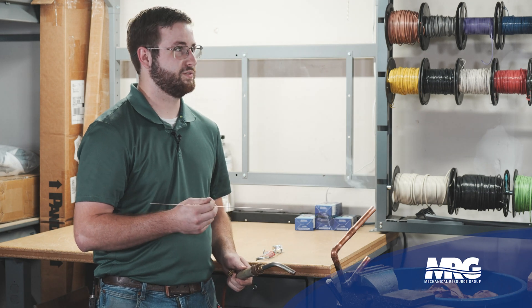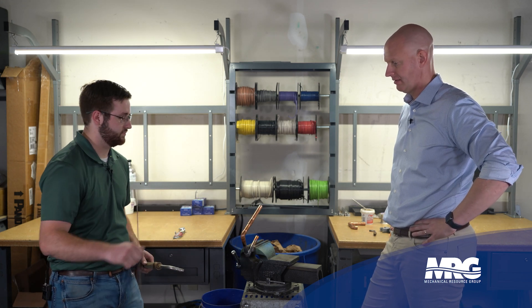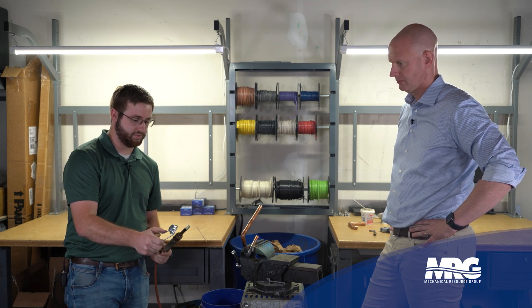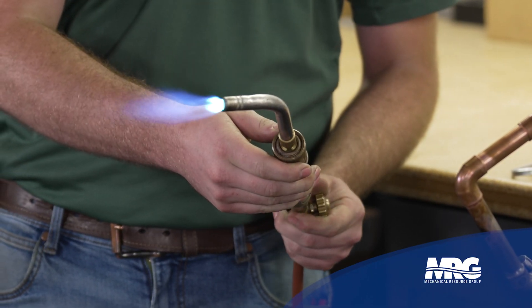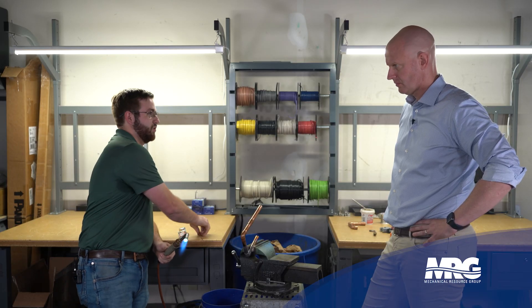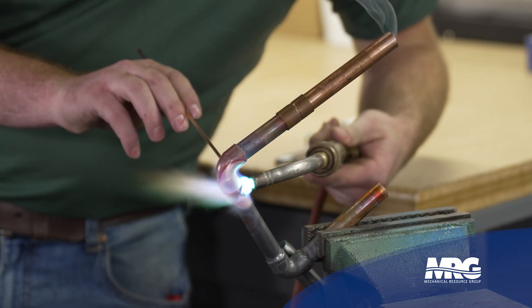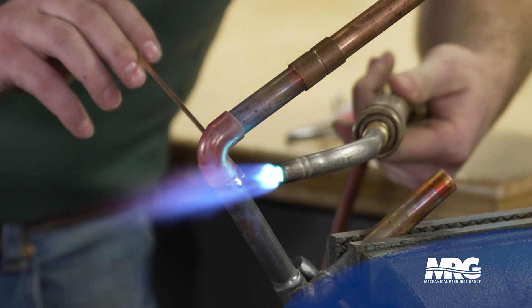You notice whenever that copper starts to get kind of — we call it cherry red. Whenever it starts to get red, that's whenever it's ready to take. Sil-Fos melts at about 1200 degrees Fahrenheit. When you strike your next torch, I want you to talk about what kind of flame you like. What we're looking for here is kind of a long blue flame. We've got kind of yellow in there — that bright blue tip right there, that's what you want. I'm going to do one more and then I want you to do one. You notice whenever it got cherry red right there, it just pulled it right in.